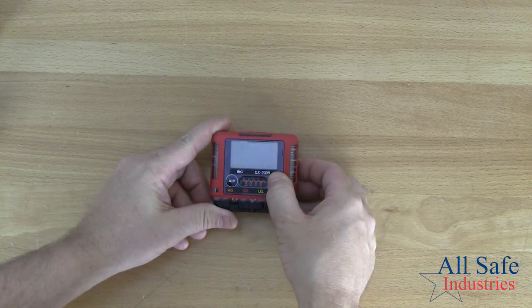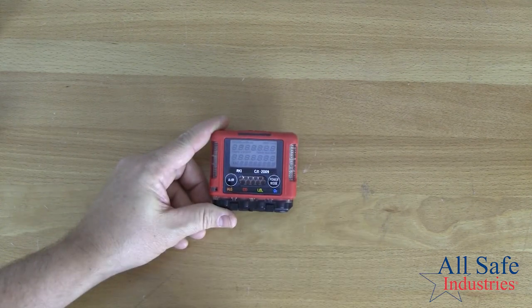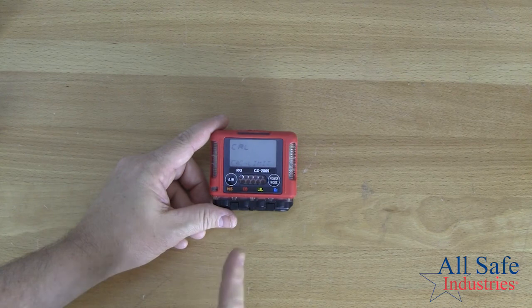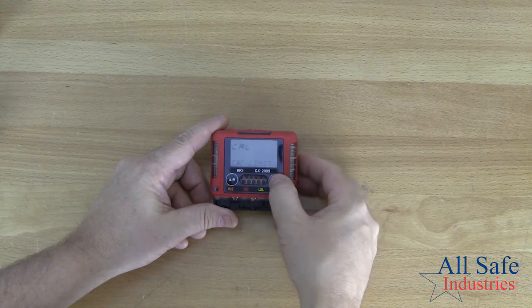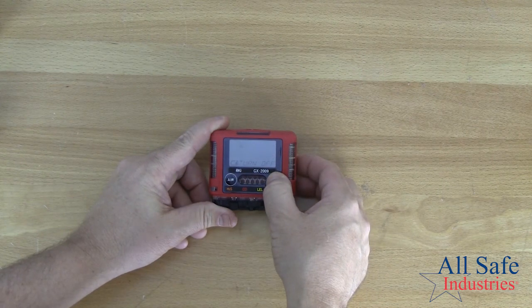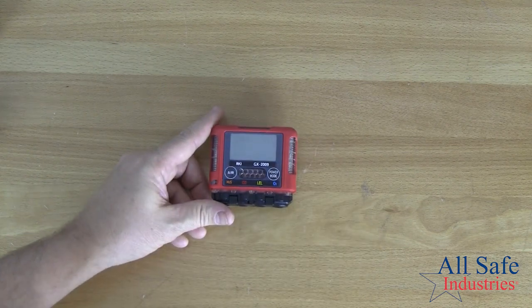I'm going to push the power mode button. The meter's going to start to warm up. And the very first screen is telling me I've exceeded my cal limit. So if I see this screen during the warm-up sequence, I'm going to go ahead and stop what I'm doing and calibrate the meter. So I'm going to go ahead and power it right back down, because to get to the calibration menu, I need to go into the menus.